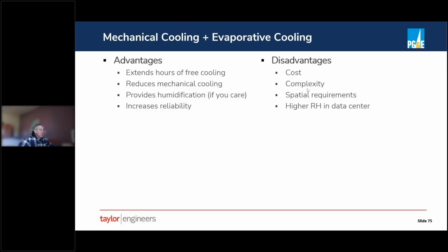As you saw, that roof was pretty much maxed out. This was a multi-story data center, and it was serving 2 floors. That's pretty much the limit, depending on your watts per square foot, that you can get with a rooftop air economizer system. Higher RH in the data center: if you're using direct evap, you are operating at a higher relative humidity. As we talked about earlier, you can still stay within an 80% maximum, or even a more restrictive one, just by limiting how much evap cooling you're doing.